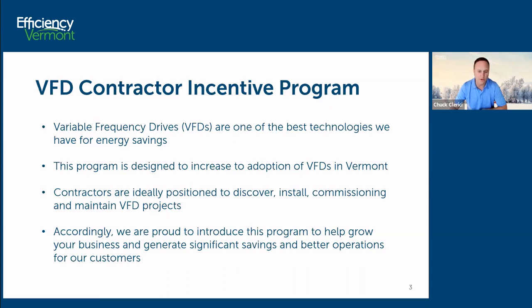There is a lot of motor load out there in the marketplace, and we'll talk about some of that in a bit. So this program was designed to increase adoption of VFDs in Vermont. I have walked through many boiler rooms and attic spaces and noticed a lot of pumps and fans out there that are still eligible for VFDs. If I had to estimate, I would say across Vermont, we're somewhere between 10 and 20% in terms of market penetration for VFDs on motors that could accept VFDs and take advantage of energy savings. The contractors in the marketplace, many of you on this call and others, are really ideally positioned to discover, install, commission, and maintain these VFD projects.